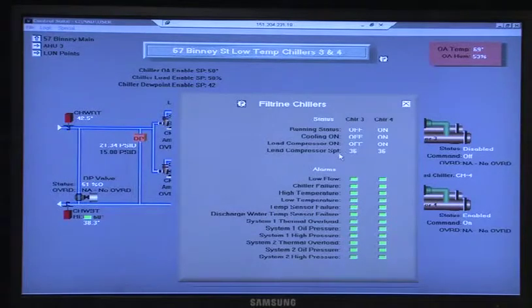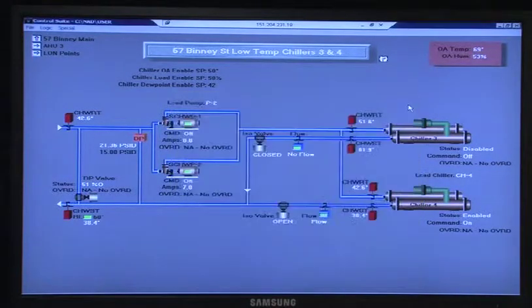Lead compressor set point. There's something inside of the chiller itself. It's a reset setting. And then alarms. This is just an alarming process. If anything goes wrong, at least we'll know, alarming on it and stuff like that. So, not a heck of a lot we do with this screen. There's not a lot of interaction. It's a lot of just alarming and point structure stuff. Not a lot of controllability. We're not really doing any controllability out of this chiller, these LON points. We're just monitoring stuff.